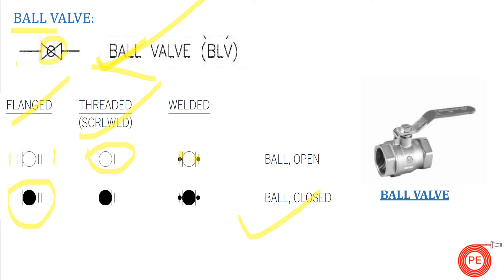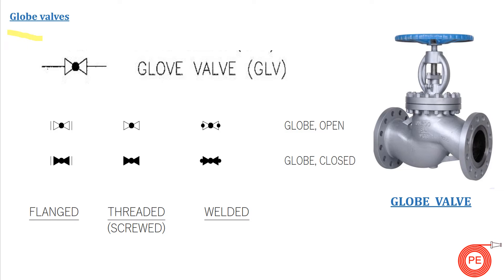Moving to the globe valve: if there is a blackish filled dot inside the valve symbol, it is a globe valve. The basic difference between a globe valve and a ball valve is that a globe valve has a filled black dot inside, while a ball valve has an open circle. Again, blackish fill means the valve is closed, and hollow means open. Two lines beside indicate flanged, nothing indicates threaded, and two dots indicate welded connection.